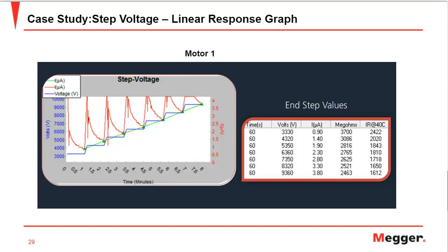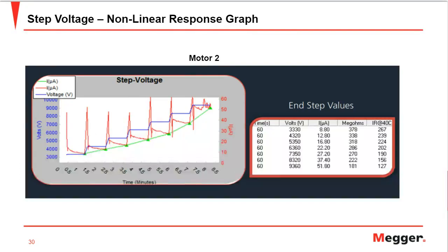While on the other hand, in this case, the graph is quite linear at this point, but as the testing goes ahead and the voltage increases, you see non-linearity here. So once we see the test results, we can calculate the differences in the leakage current, and then determine the non-linearity from the graph as well, which helps us understand that the insulation is not so good on motor 2. This was a case study done.